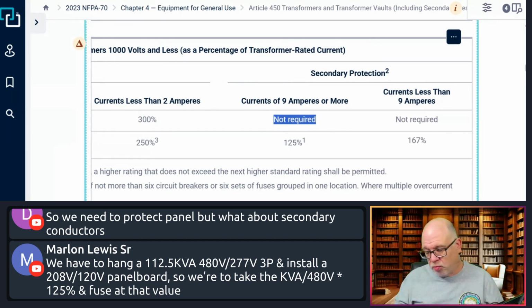There are other rules in the code which will say, well, I still need to protect my panel board, right? But you saw where there was an exception where that panel board could be protected by the primary only under the exceptions in 408.36(B). Very rare. I don't think in my career I have ever seen where the primary protection that protects the transformer only, and it's not a requirement for the secondary, would have a panel board, and under 408.36 require protection for that panel board, but under the exception, it will say, well, wait a minute, I don't need individual protection for that panel board if you follow all the rules and it's protected on the primary side, okay?